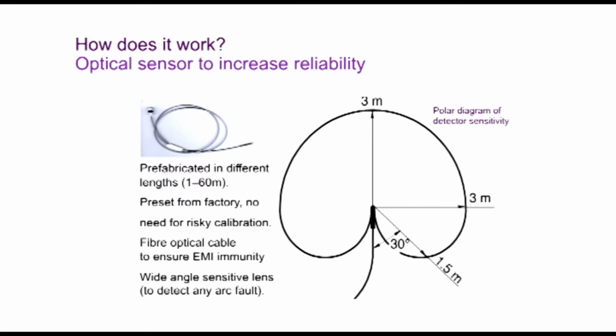Basically, what is the radial sensing of the sensors? They operate up to about 3 meters. It's a radial optical sensor where there is a slight bend at a 30 degree angle. That radial sensing would be limited to about 1.5 meters. The good thing about these fiber optic cables and detectors is they're prefabricated at the factory, so you reduce the risk of calibration. You can have lengths of 1 meter, 2, 4, 6, 8, all the way up to 60 meters. And because it's fiber optic, you have immunity against electromagnetic interference.